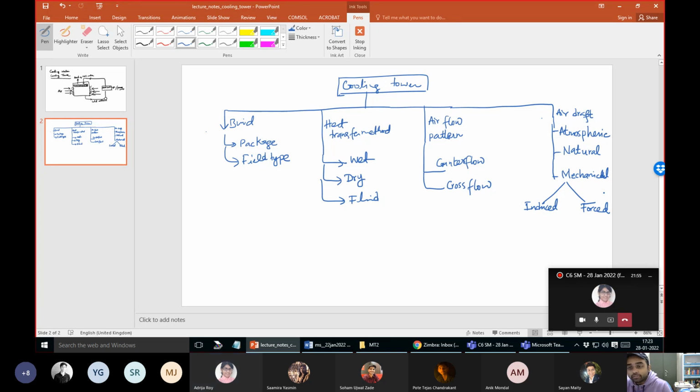No, just do not get confused. In the shell and tube exchangers, you cannot cool the cooling water. Whatever cooling water we use in the shell and tube exchanger has to come from some other source. In heat exchangers, normally the operations we do are restricted towards ambient temperatures. Otherwise, we have to use some refrigeration, right? The cooling water temperature is normally 30 or 35 degrees in the Indian context. If you use that cooling water in the heat exchanger, the temperature will not drop below 40 degrees. So now the question is how to get this cooling water.